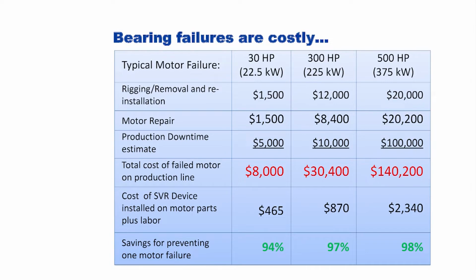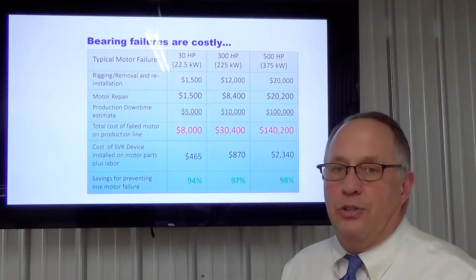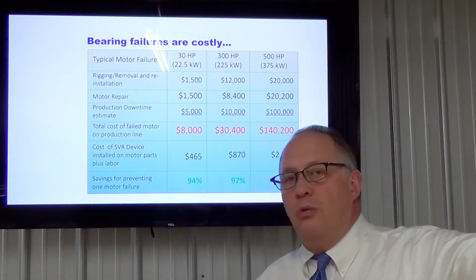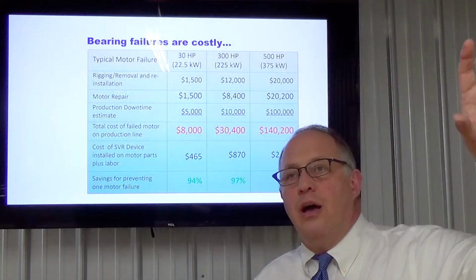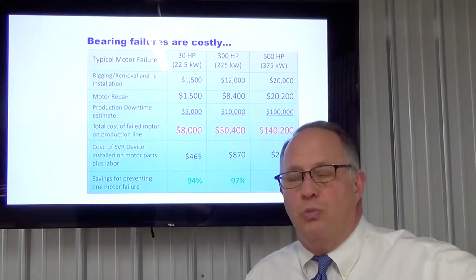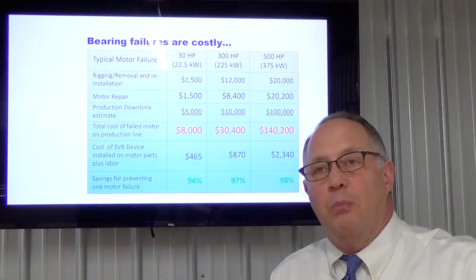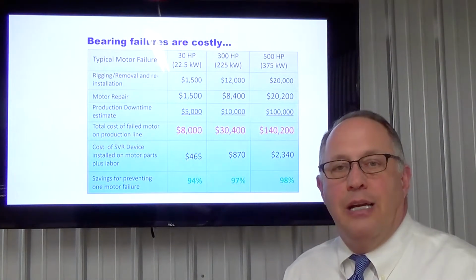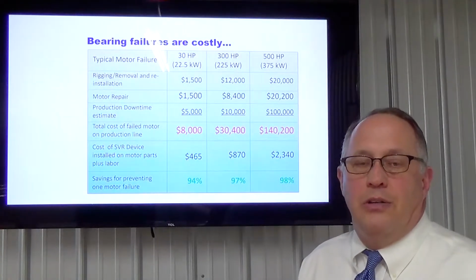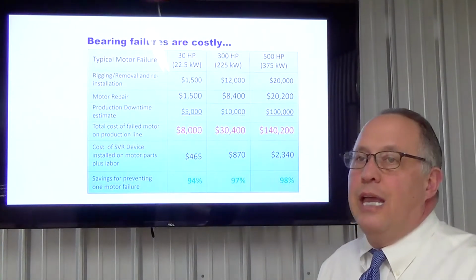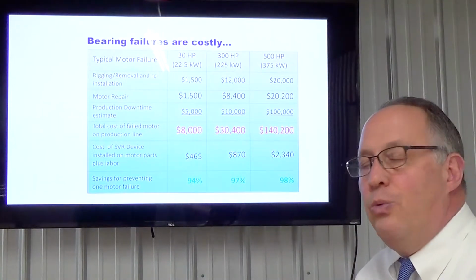Bearing failures are costly. As we can see here, typical motor from 30 horsepower, 300 and 500 up. Obviously, the larger the motor, the more expensive it is. The higher the repair, anywhere from $1,500 to $20,000. The downtime can be even more catastrophic. If we were, say, for example, I'm going to show in a field operation where HVAC was on a continuous running research, and if that particular motor failed, they would end up shutting down an entire research project that's been ongoing for 2 years. You can't replace that. Those are valuable. How do we get away from that?